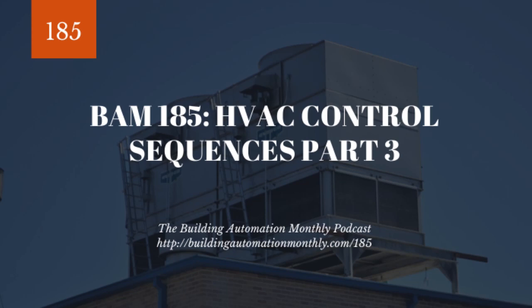And the reason why is, oftentimes, when folks are new to this field, they'll say, oh, economizer, it's 65 degrees outside, I'm going to control with the economizer. It's great, awesome, free cooling. And then they don't look at, like, 65 and 90% humidity. I know those are some crazy wonky numbers, but what you have to realize is as temperature increases, the effect of relative humidity is massive. So the amount of moisture, grains of moisture per pound of air, at 55 degrees with 100% relative humidity is completely different than at 90 degrees and 90% relative humidity. As air gets hotter, it can store more moisture in it.